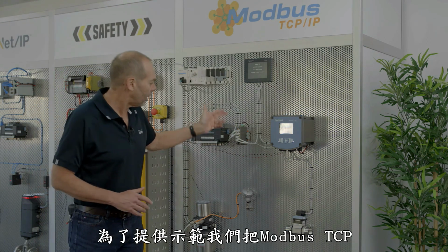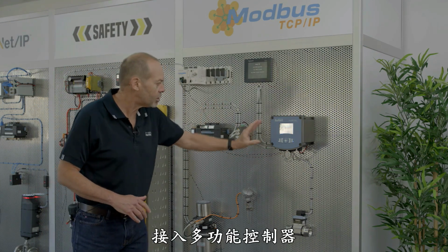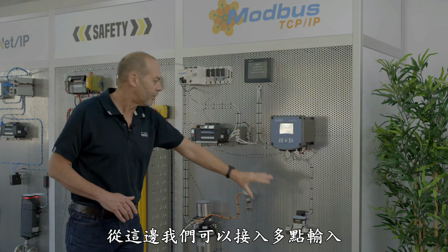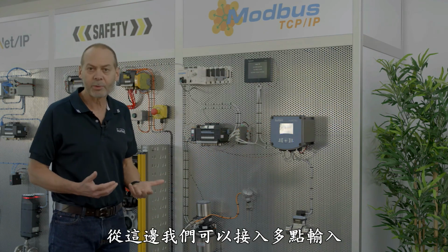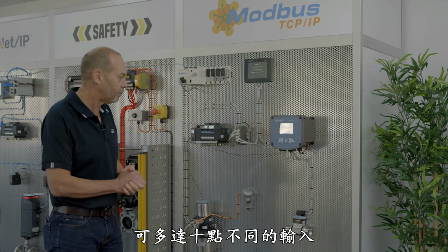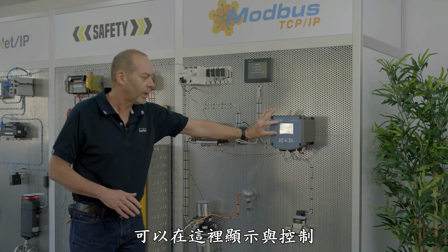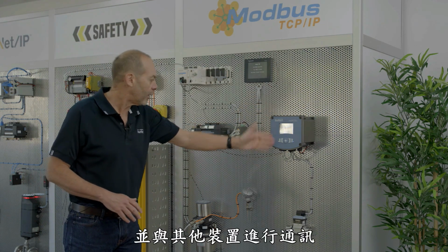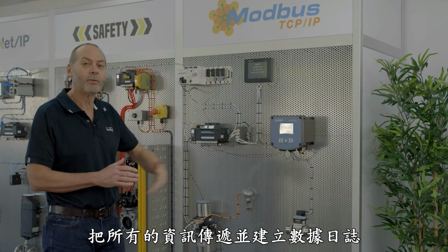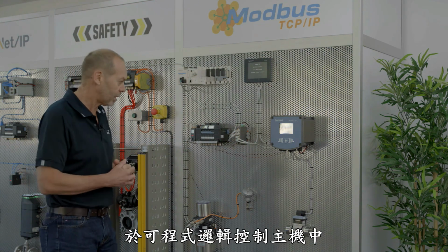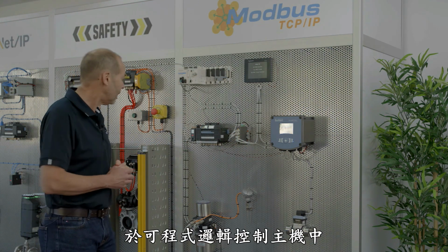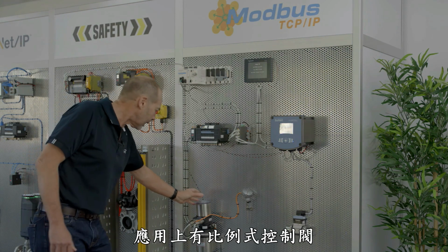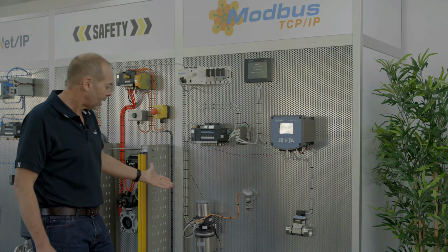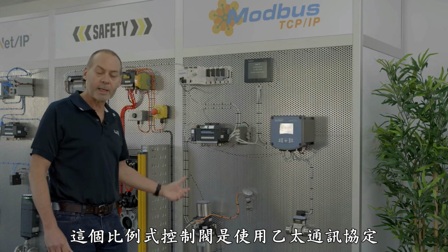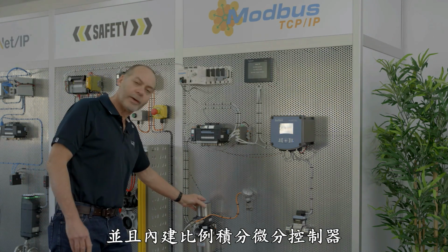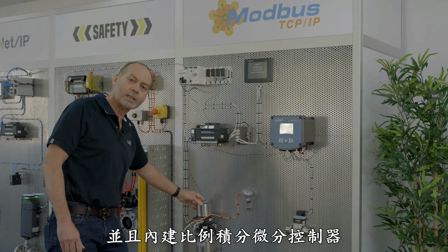To give you an example, we bring the Modbus TCP into our multi-cell controller. From there we can take in a number of different inputs, probably up to 10 different inputs into one controller. We can display them, we can control, and then we can communicate all of that information back and do data logging, etc., back in the main PLC. Also applications like our modulating control valves. This is a modulating control valve speaking Ethernet directly and also has an inbuilt PID process controller.